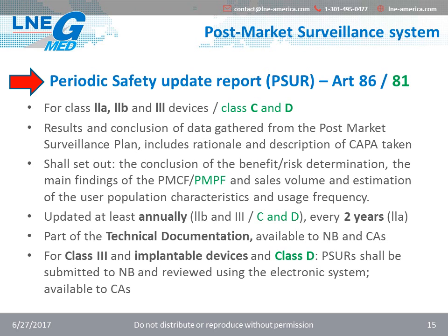The second type is for Class 2A, 2B, and 3 devices, and for IVDs Class C and D. The manufacturer shall prepare a periodic safety update report, also called PSUR. As for the post-market surveillance report, the periodic safety update report shall present results and conclusion of data gathered from the post-market surveillance plan and includes rationale and description of CAPA taken.